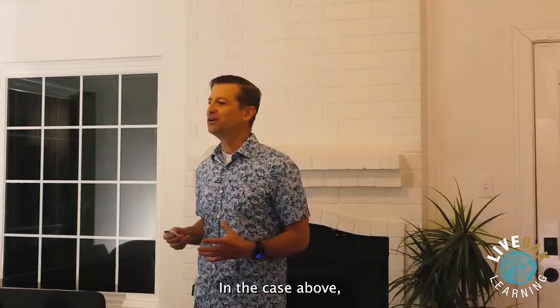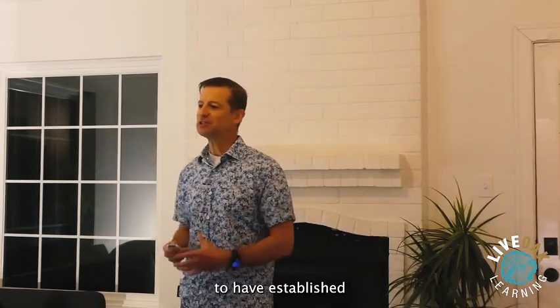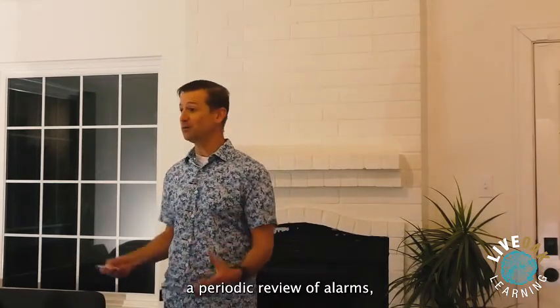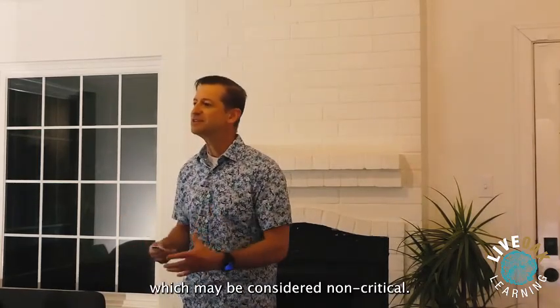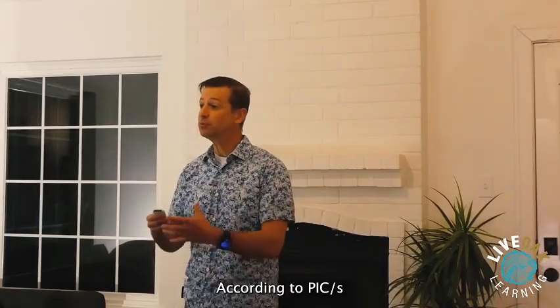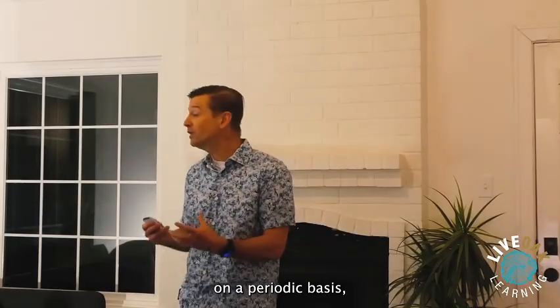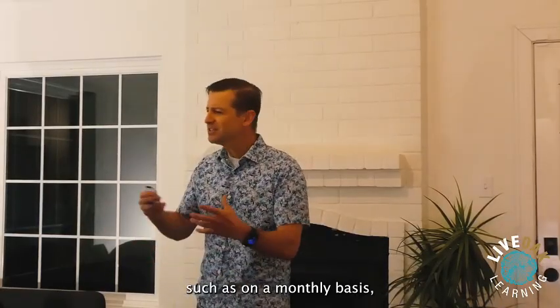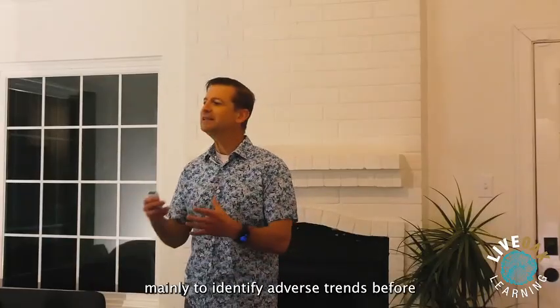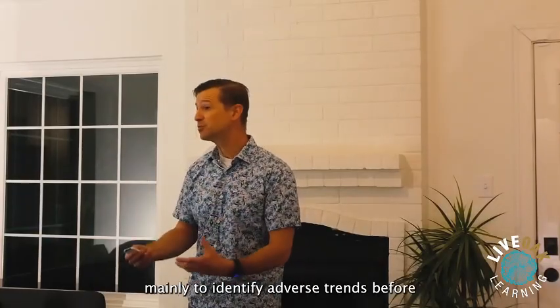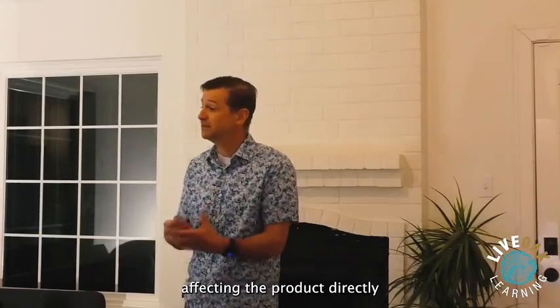In the case above, the firm appears to have established a periodic review of alarms, which may be considered non-critical according to PICS and therefore reviewed on a periodic basis, such as monthly, mainly to identify adverse trends before they become an issue affecting the product directly.